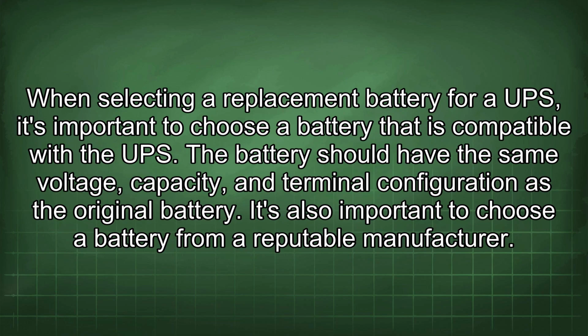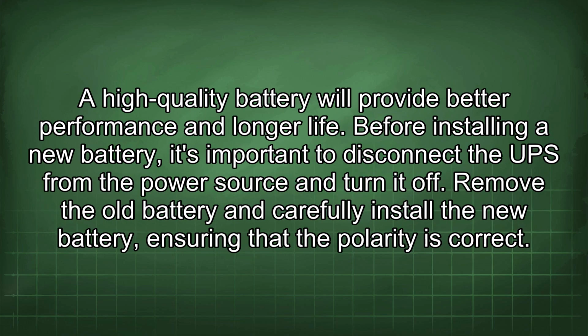When selecting a replacement battery for a UPS, it's important to choose a battery that is compatible with the UPS. The battery should have the same voltage, capacity, and terminal configuration as the original battery. It's also important to choose a battery from a reputable manufacturer. A high-quality battery will provide better performance and longer life.